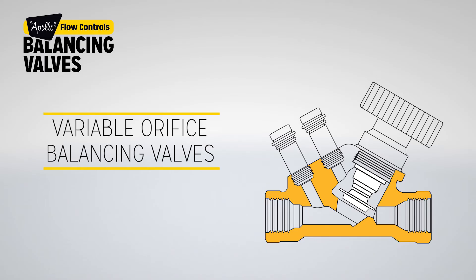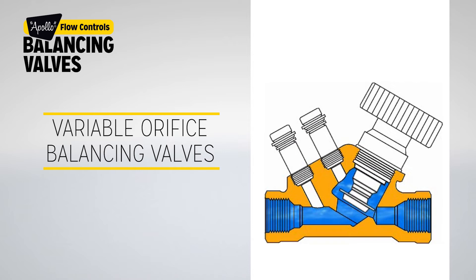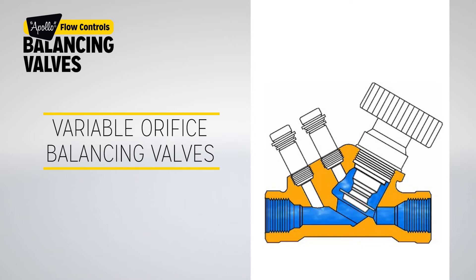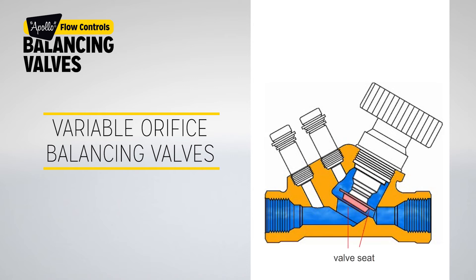Variable orifice balancing valves: a variable orifice double regulating valve is designed to permit measurement of the flow by measuring the differential pressure across the seat of the valve. The Cv changes each time the setting is altered. A variable orifice double regulating valve is recognized by the position of its measuring points, situated on either side of the regulating disc to measure flow across the valve mechanism. It is characterized by the feature of measuring the flow rate across the seat of the valve.